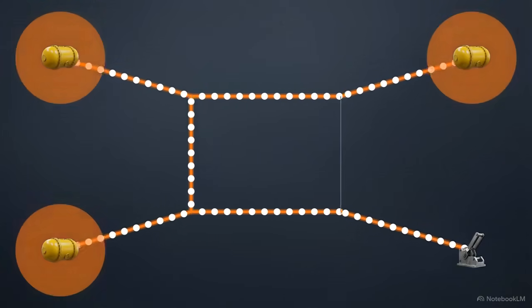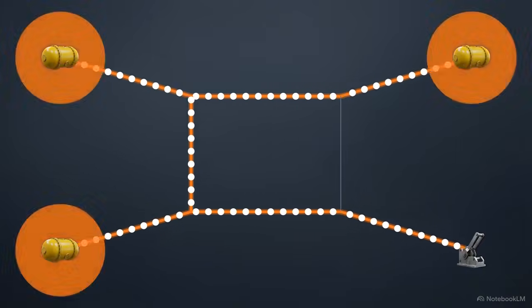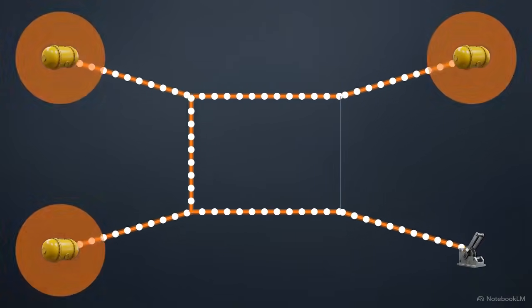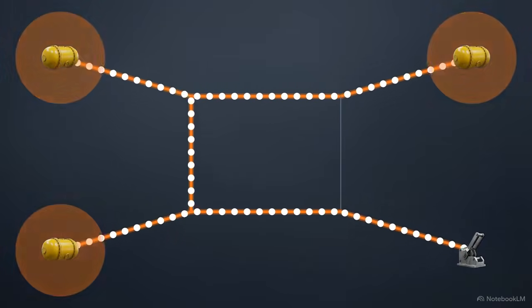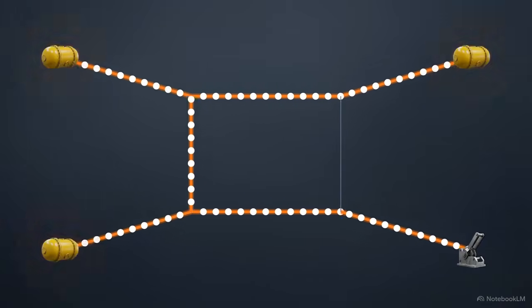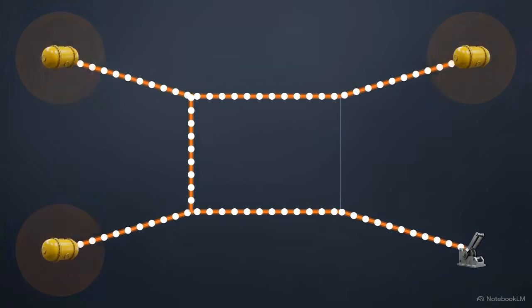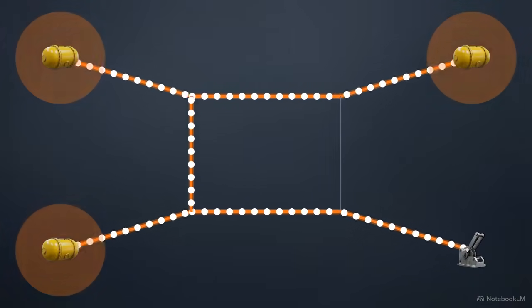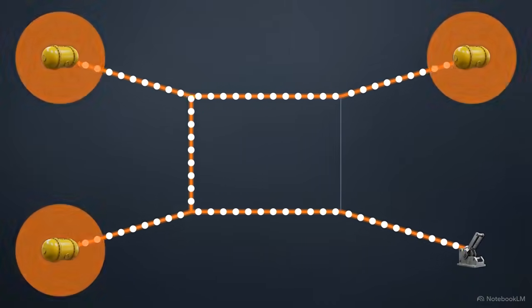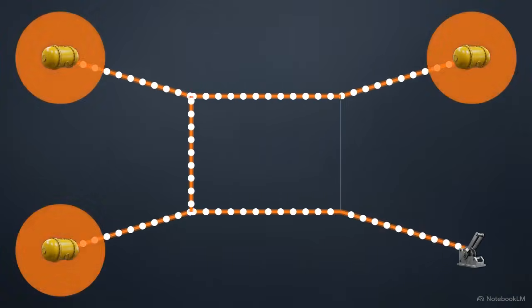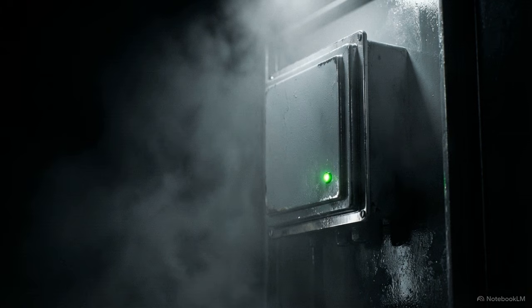A short circuit drops the voltage on a specific line to zero, creating an electrical vacuum that rips current from its path, pulling massive energy toward a single exit point. Standard generators are forced to push out current exceeding 20 times their normal output, shoving a tidal wave of energy into the breach. By 0.06 seconds, the grid's protection relays intervene.